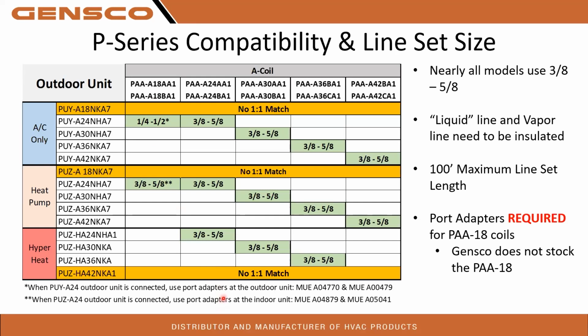So if you're using the port adapters on the PUY, your port adapter is going to go on the outdoor unit. That way you can reduce the line set size going to the coil. If you're using a PUZ, you're going to use your port adapters on the indoor unit. That way your line set size will remain 3/8 by 5/8.